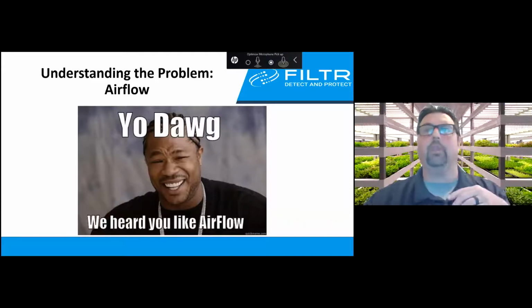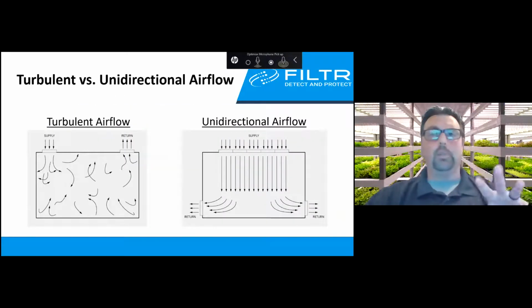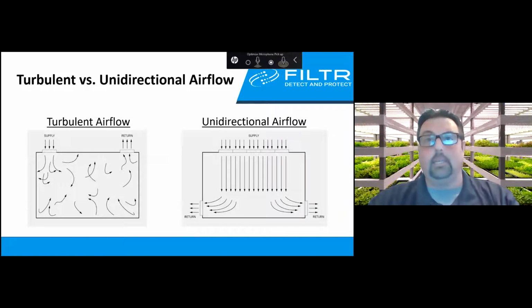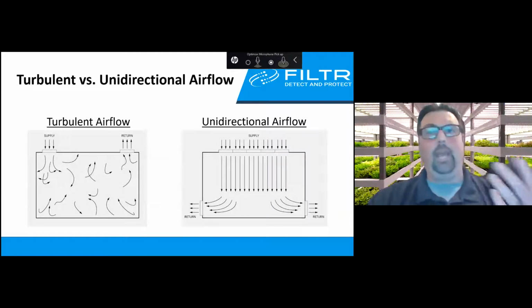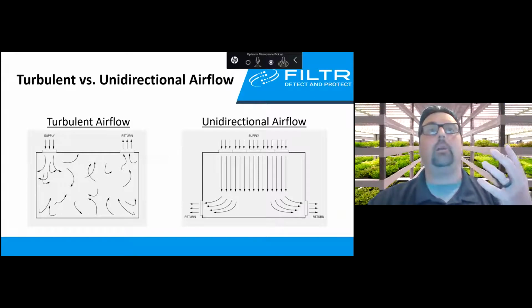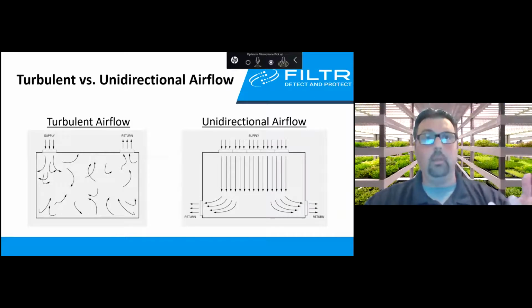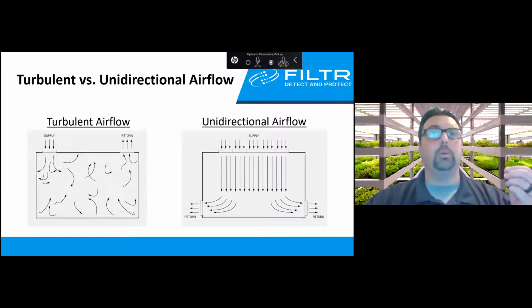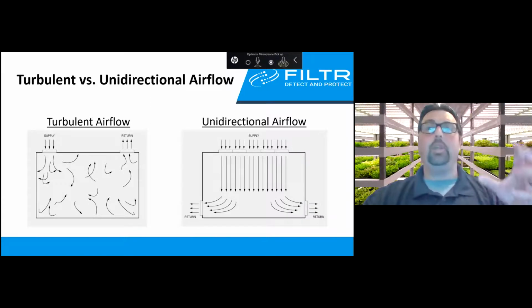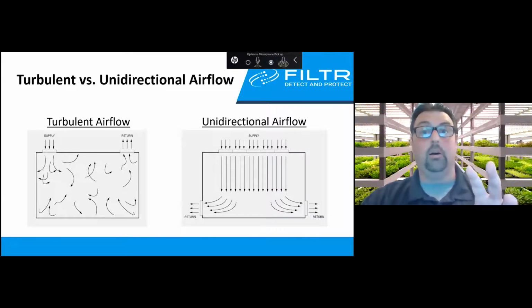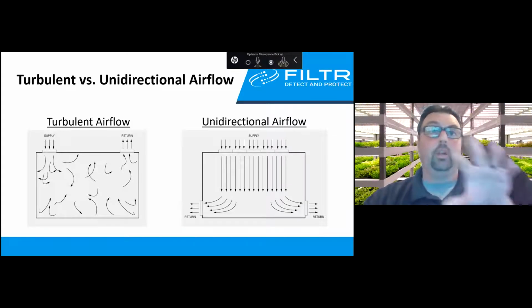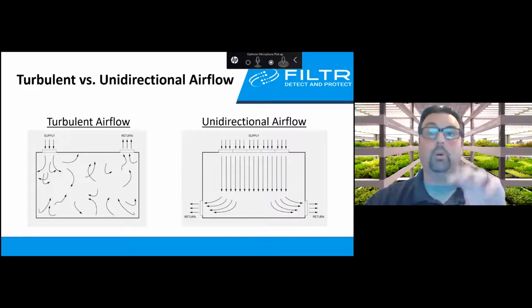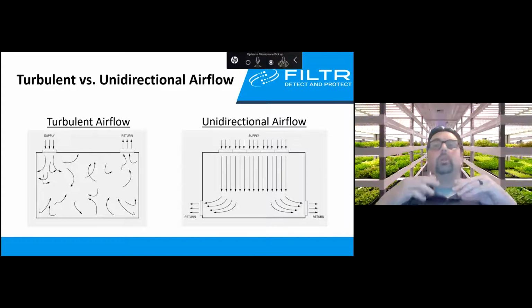Let's move on to airflow. Here's what's going on, and here's what's ideal. In cannabis, we typically operate under what's called a turbulent airflow environment. That includes the HVAC system pumping in from the ceiling or from a windsock, however your HVAC is set up, plus a lot of supplemental fans blowing air around the room to keep air off the plants and prevent powdery mildew.